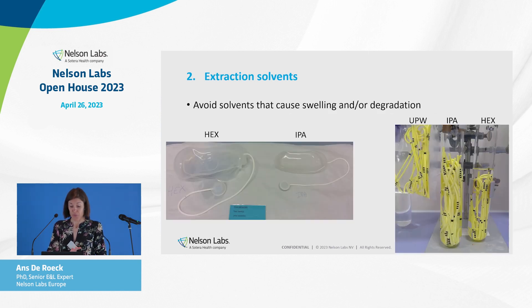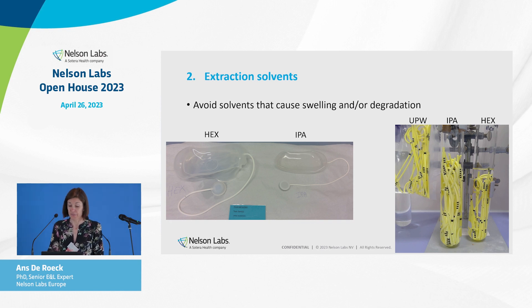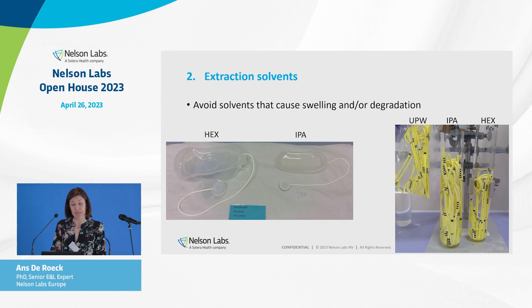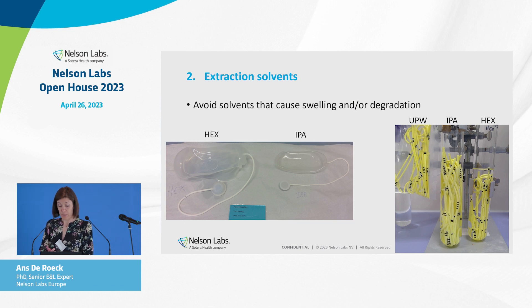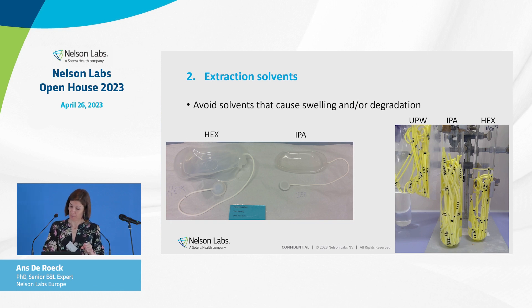We also have to avoid solvents that cause swelling or degradation. A typical example is silicone devices that swell extremely in hexane, or polyurethane tubings that swell in the semi-polar solvent isopropanol.